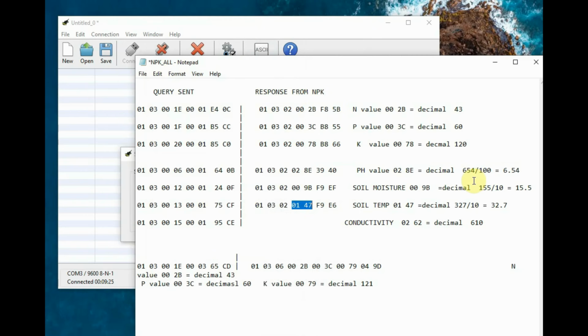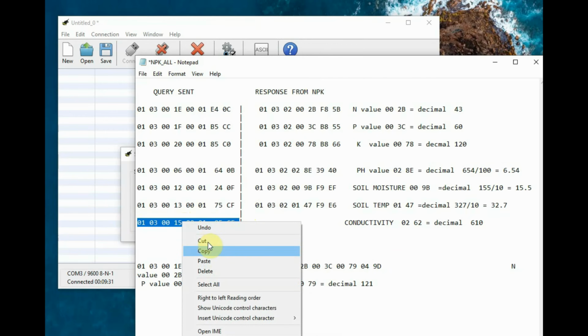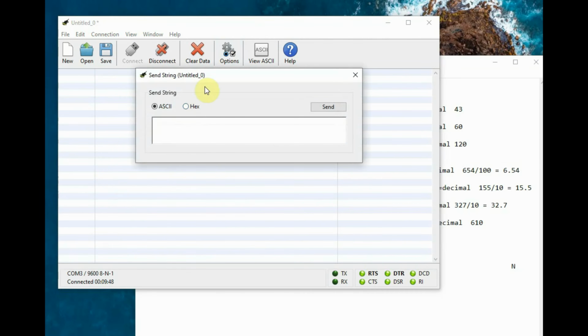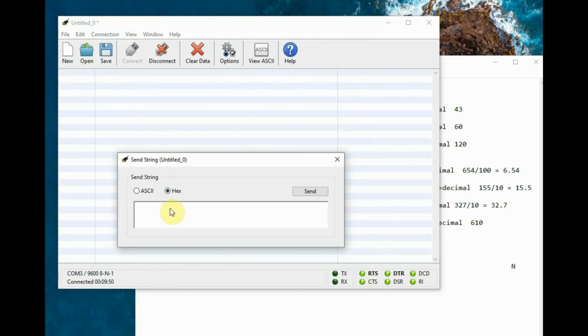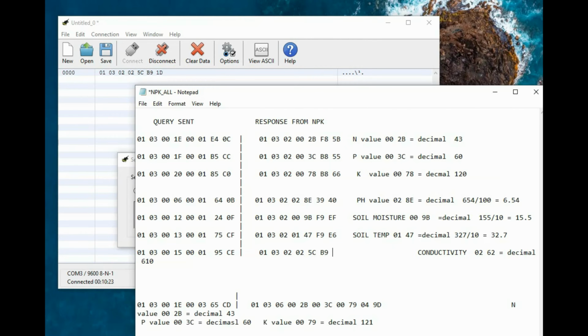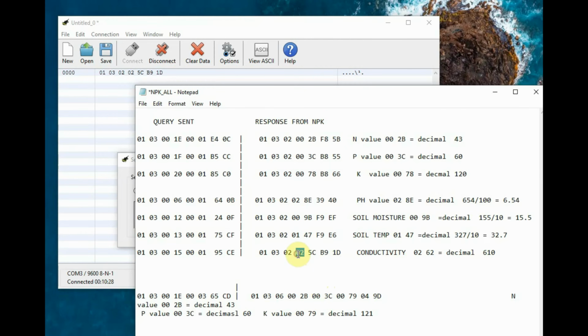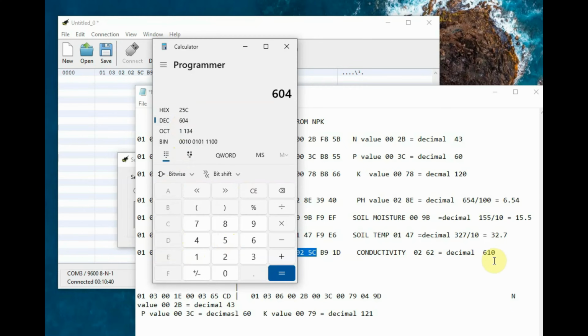And for the soil temperature, paste the query data and get the return data. The 4th and 5th byte, you convert it to decimal and then divide by 10. It is 32.7, which is the soil temperature. Finally, for soil conductivity, paste the query code and get back the result. The 4th and 5th byte is the electrical conductivity. It is in microsiemens per centimeter, no division here. So this is how to analyze using the query send data.